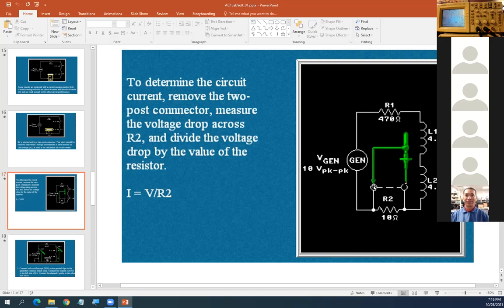Hey, Mr. Pham, I don't know if you really care or not, but if you have a DMM, then you could also break the circuit and measure the current. Exactly. You can measure the AC current, RMS. Connect high side here, low side here. Make sure your meter is connected to measure the current.